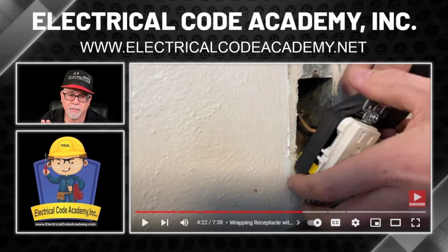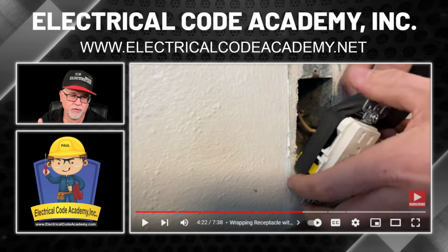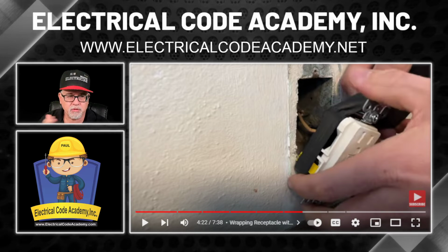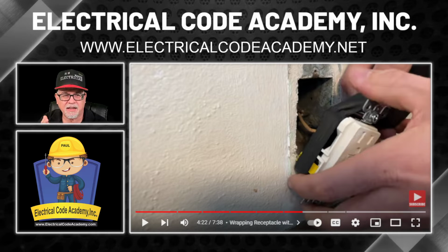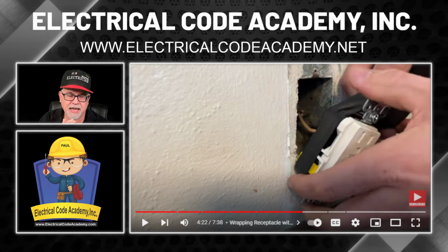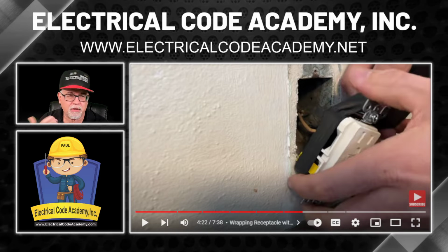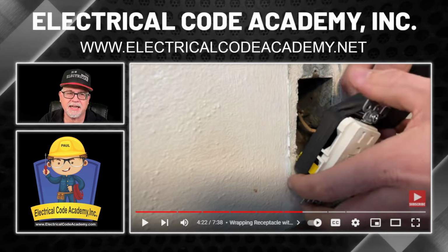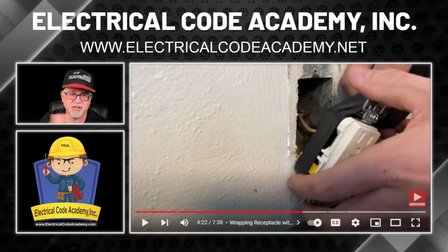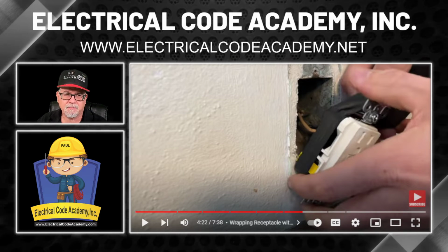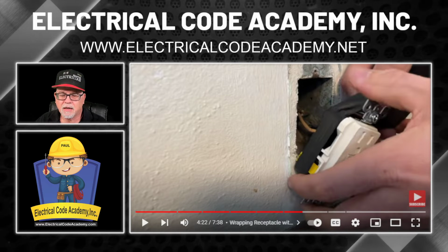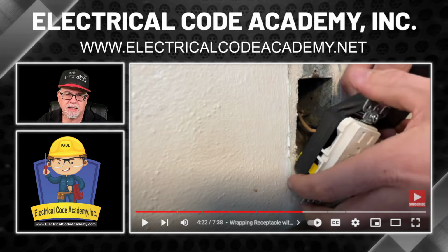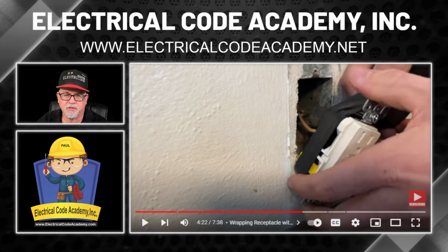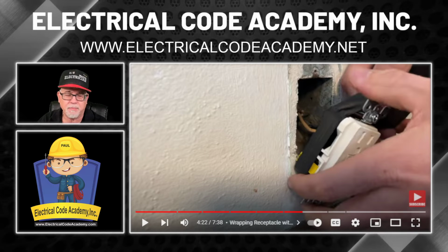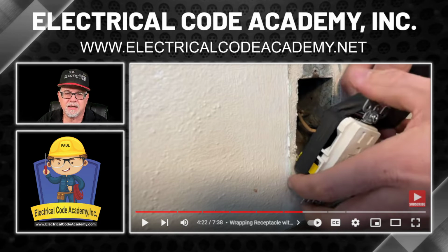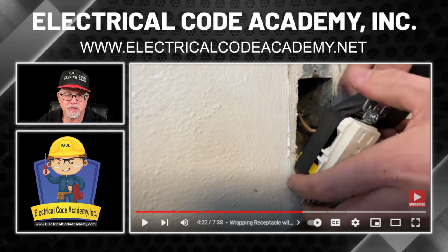So this is not required by code. This is very common. People that work in commercial like to do this a lot. It's actually designed, where the screw is, the mounting screws, so that the side of the device could not get to the edge of the box. Again, it is a bigger deal when you have a bunch of equipment grounds in a box and you're tucking everything back in the box, and I get it. But it's really designed so it should not touch the side. There's absolutely nothing wrong with adding the tape. Again, go for it if you want to do that. It's a preference. I installed many devices in metal boxes and never had the issue, and I did not wrap with tape. But feel free to do so if you want to. That's perfectly an acceptable practice for you to do if you would like to.